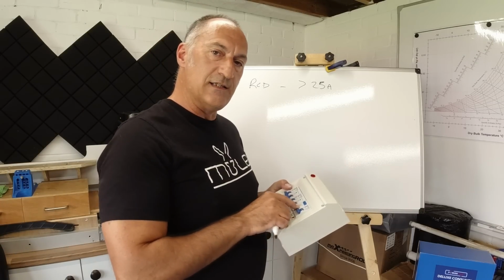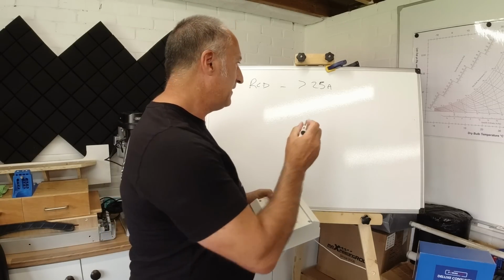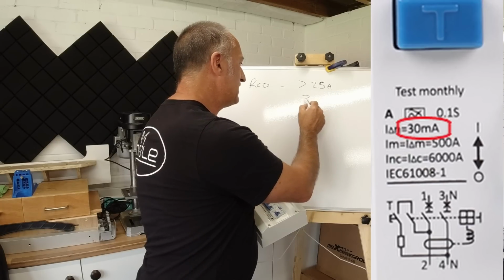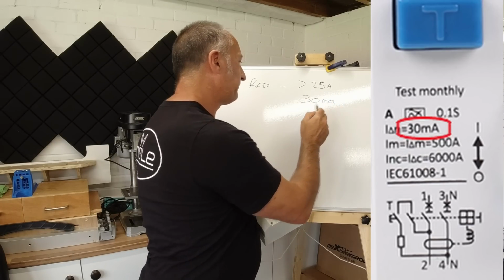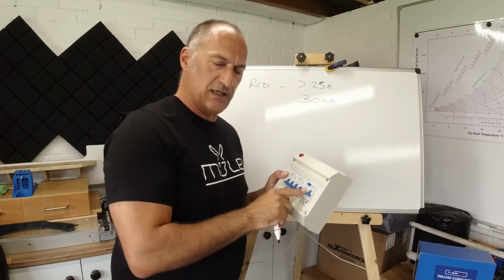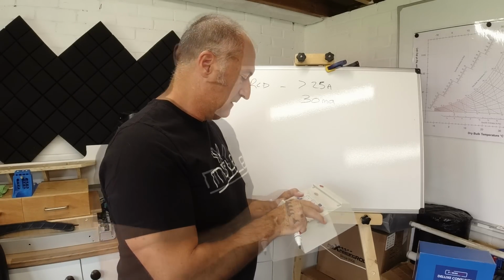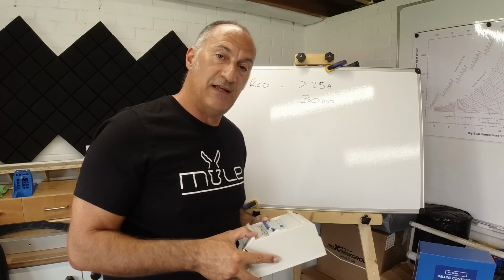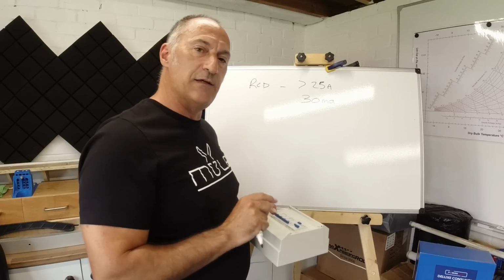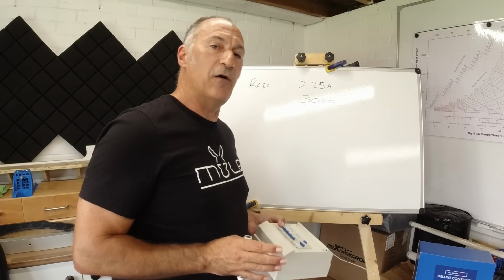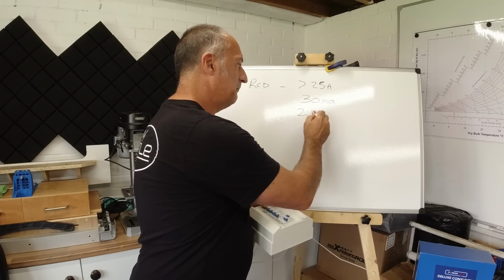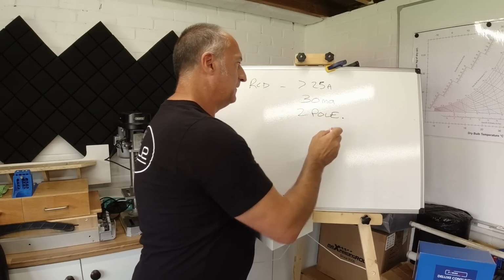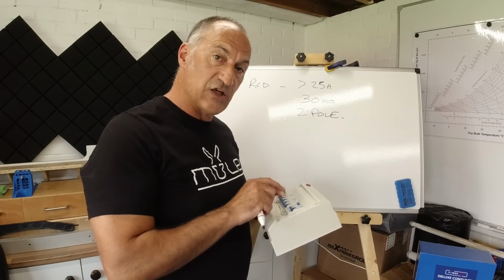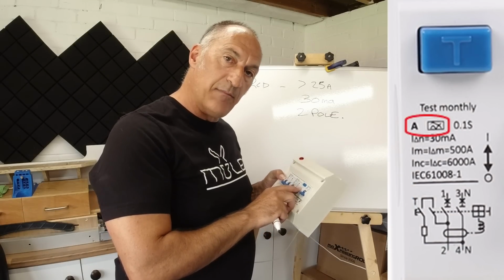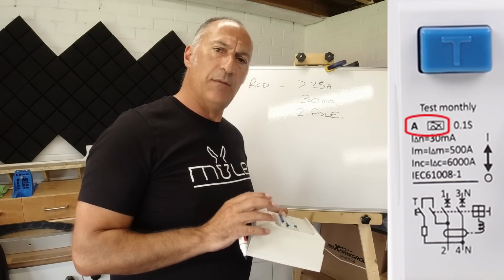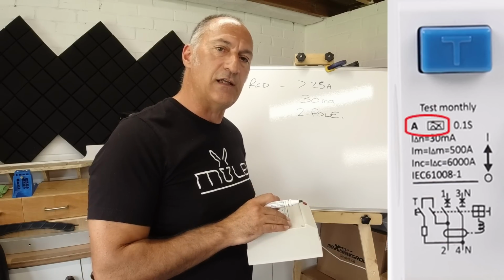The thing to look out for is the level at which it breaks at. And for our purposes, to comply with the regulations, that needs to be 30 milliamps. And most of the RCDs that you'll find will be 30 milliamps. And then for the purposes of our installation in a camper van, to comply with that 721 regulation, it needs to be a double pole RCD, so it needs to break both the line and neutral. And to be honest, most of them are two pole RCDs. And then lastly, it has a type on here, and in this case it's type A. And what that refers to is the type of connected loads that you've got downstream of the RCD.